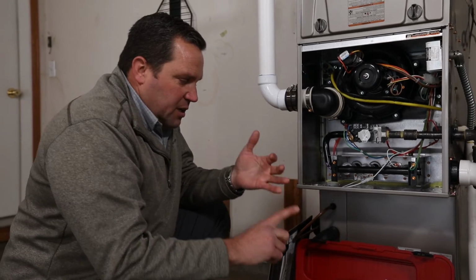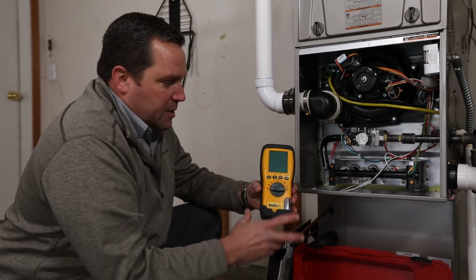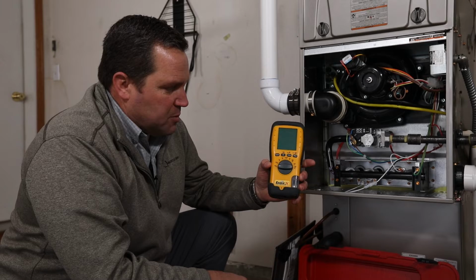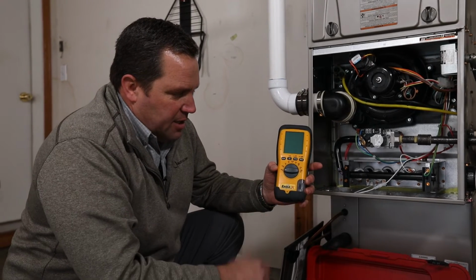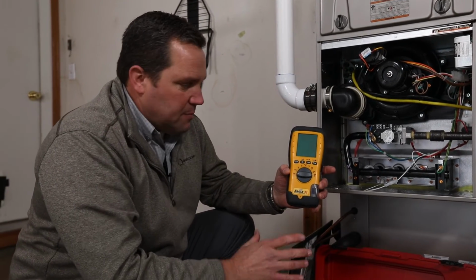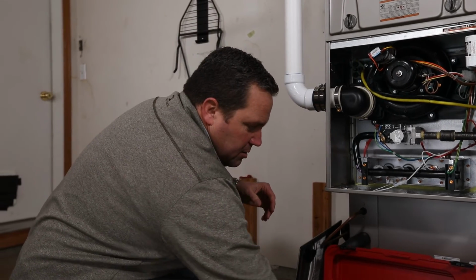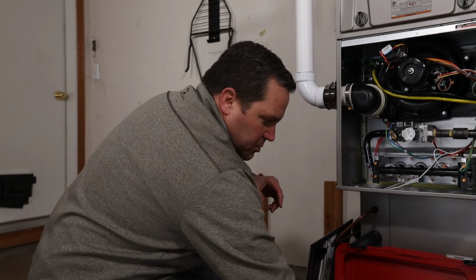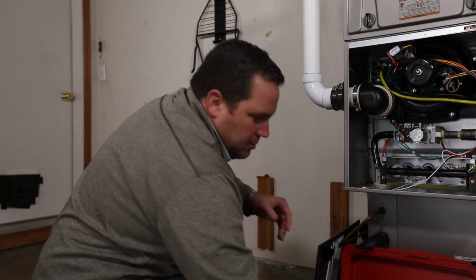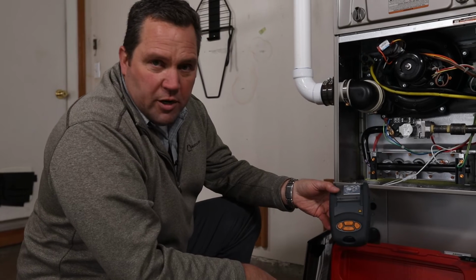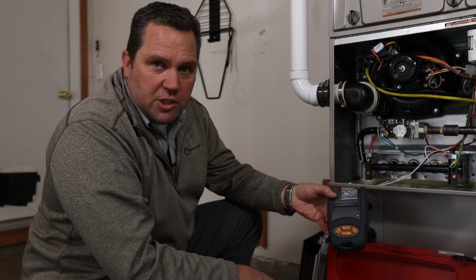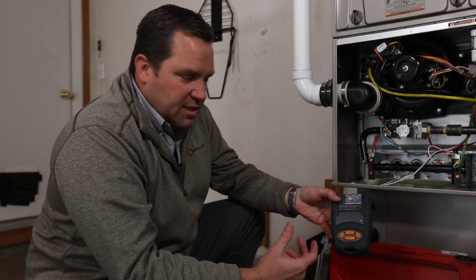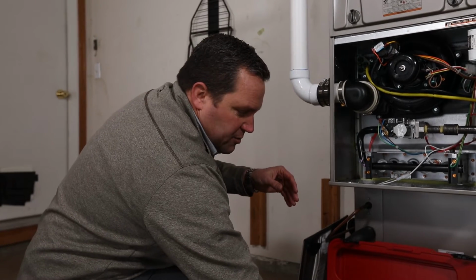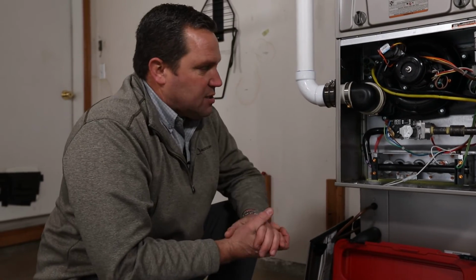And then the other thing that we can use is what's called a combustion analyzer. This one is made by UEI. It's the Eagle 2X. It's a great system. It will give us the amount of unburned gas that's happening in that system. What's really nice is it comes with a portable printer, which we can print out, and then we can show that to the homeowner so that they can see exactly what we're talking about as far as the amount of gas that's being released, because the last thing you want is carbon monoxide getting into your system.